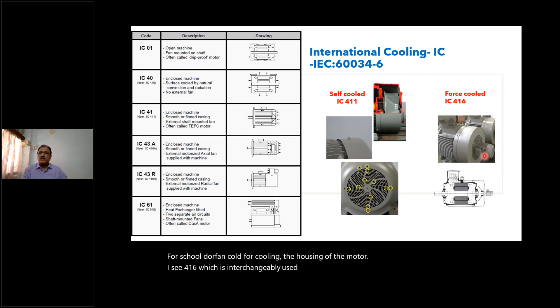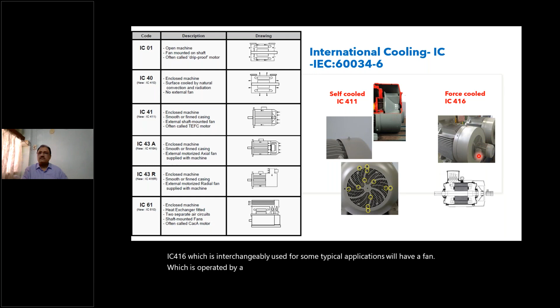IC 416, which is interchangeably used for some typical applications, will have a fan which is operated by a three-phase motor. So this is the fan cover. There is a fan, but that fan will be operated by a separately operated motor. So this is mostly useful for VFDs, where you might use a VFD supply from the main terminal box and use a constant 50 Hertz supply from the auxiliary motor. So these are called IC 416.